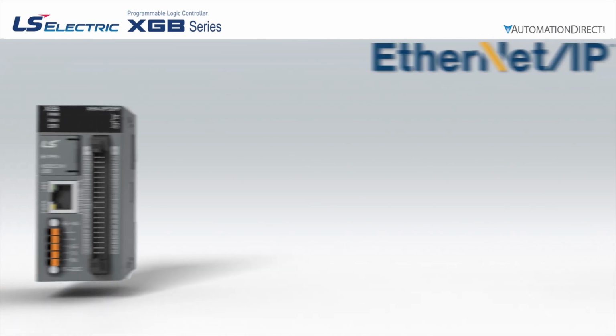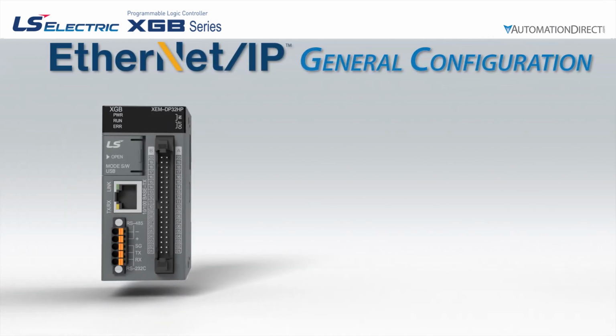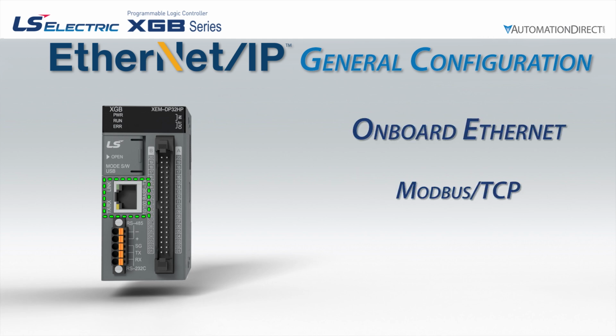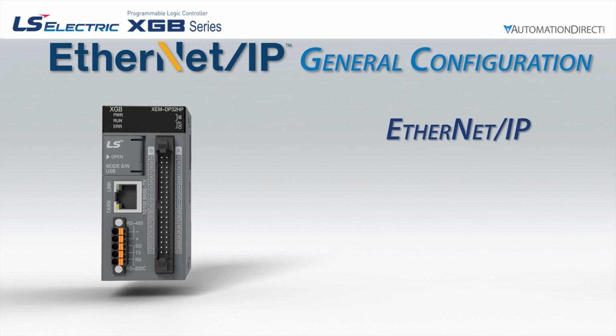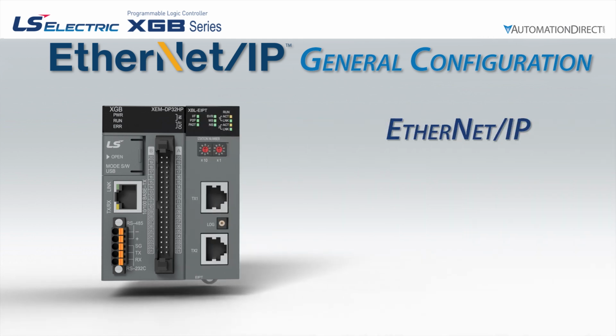The XGB PLC offers many ways to communicate over Ethernet. The onboard Ethernet port allows Modbus TCP and XGT protocols. But to use the Ethernet IP protocol, we must use the XBL EIPT expansion module.